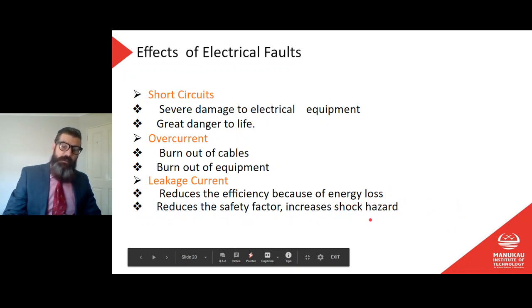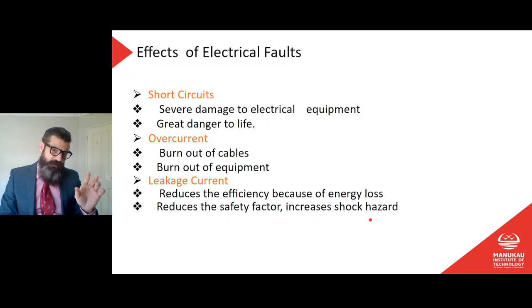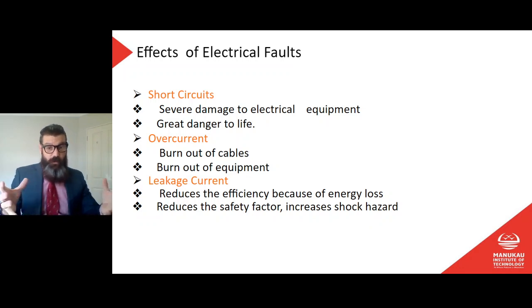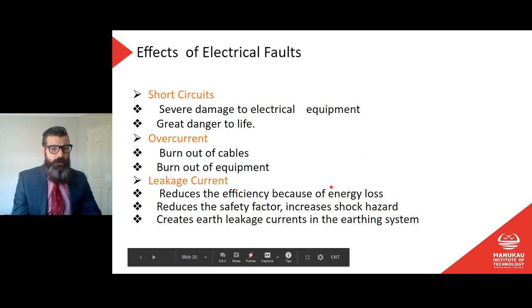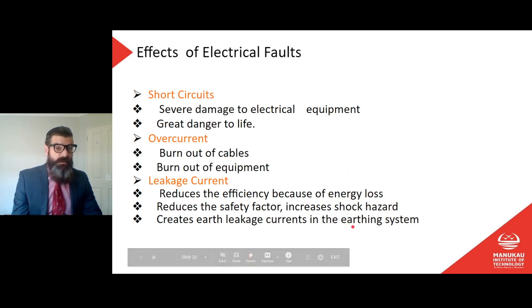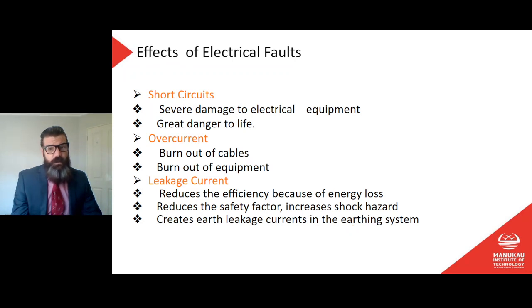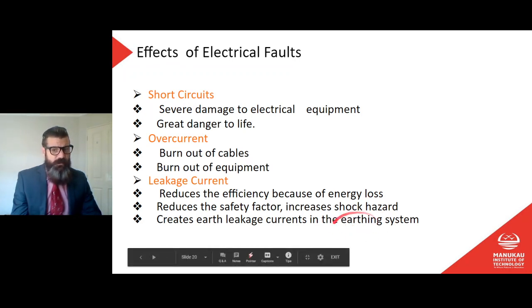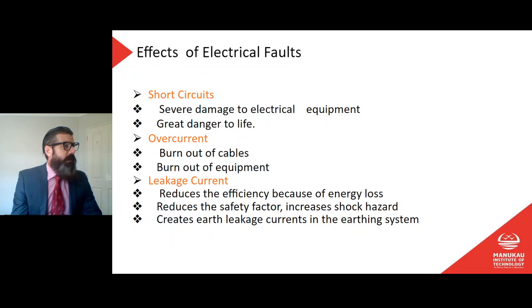And it reduces the safety factor and increases shock hazard, because if we've got a leakage current to earth, then we must also have voltage present upon our earth wire or on the earthed body of an appliance or a piece of equipment. So then there's a safety hazard there as well. It might not be a high voltage, maybe it's a very low voltage in the case of a small leakage, a high resistance pathway to earth, but there's a potential shock hazard there because now we've got a voltage on the earth. And it creates earth leakage currents in the earthing system, which is not ideal, which means that we've got current running in our earthing system, which is not designed to be carrying current most of the time. Okay, that is the end of that.